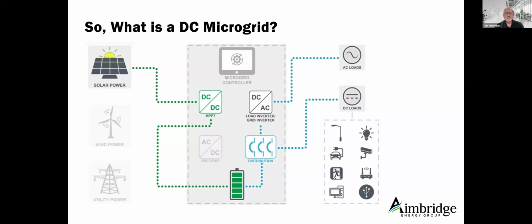In the lower right, you can see icons representing loads that can be fed with direct DC instead of traditional AC. In the upper right, you'll see AC loads fed with an inverter system that converts DC to AC. Every building has legacy AC loads that can only be AC fed devices, so this configuration allows us to feed some loads with traditional AC by inversion, while preserving the goal to have the majority of loads actually powered by DC instead of AC.